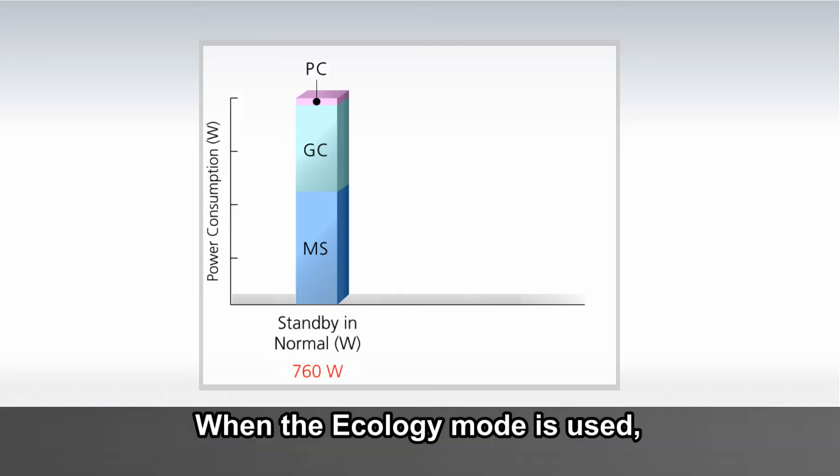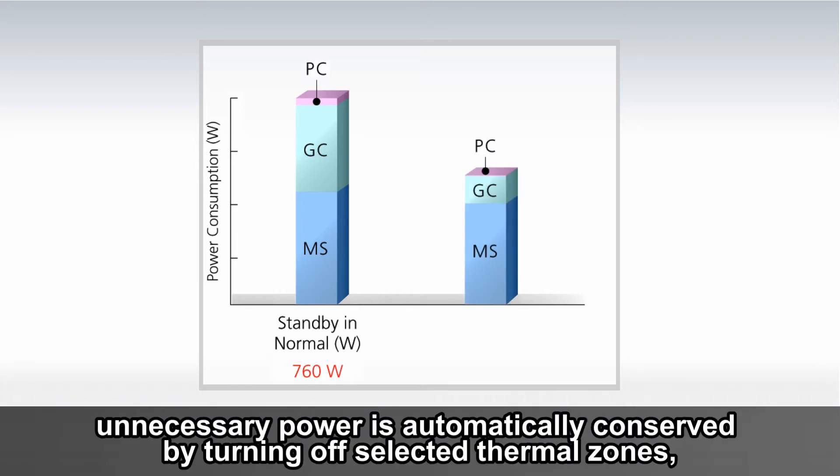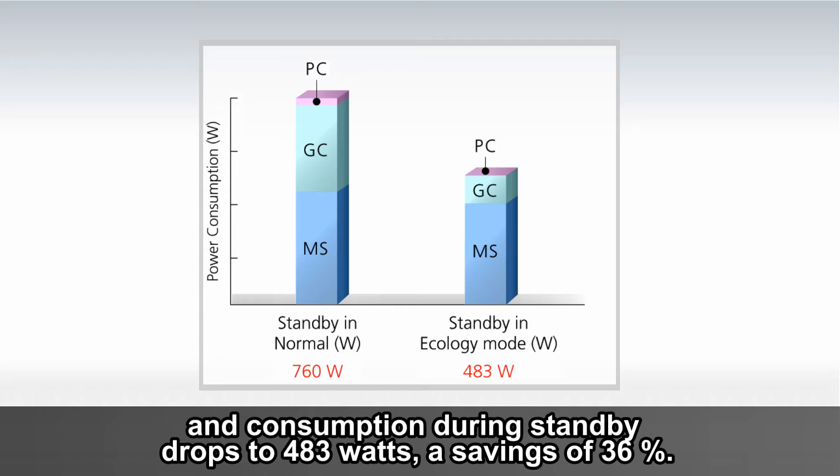Normally during standby, power consumption by the GC, MS, and PC units is 760 watts. When the Ecology Mode is used, unnecessary power is automatically conserved by turning off selected thermal zones, and consumption during standby drops to 483 watts, a savings of 36%.